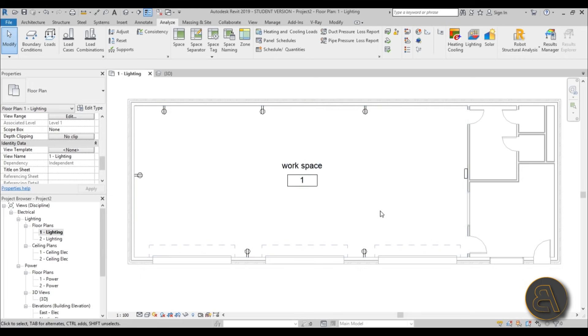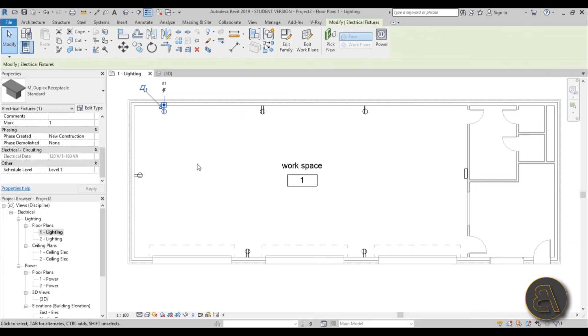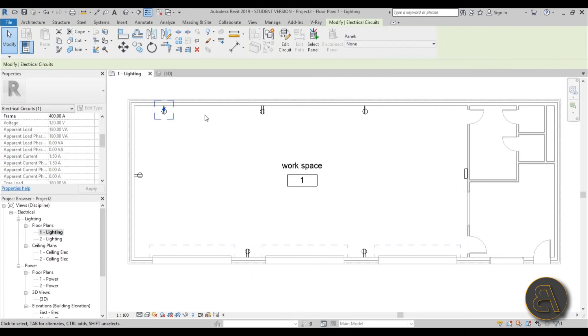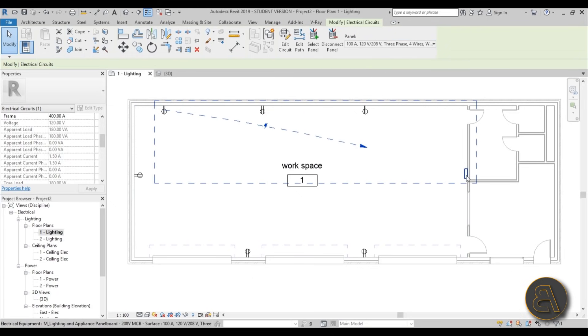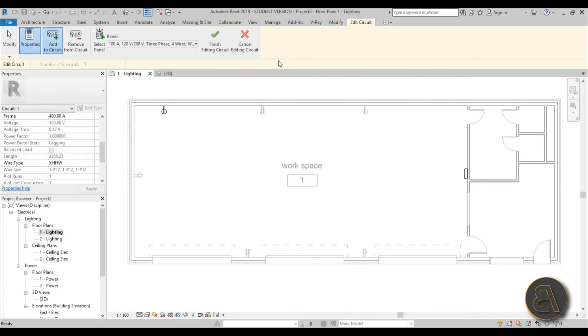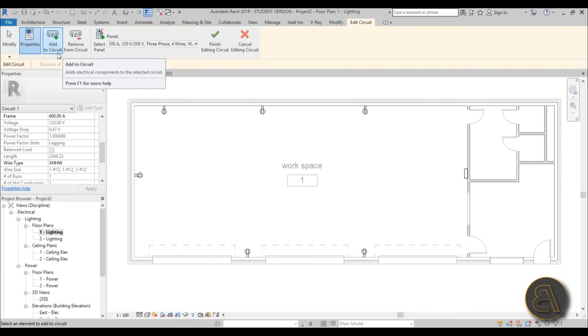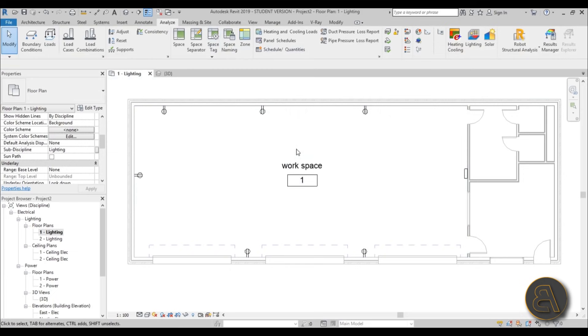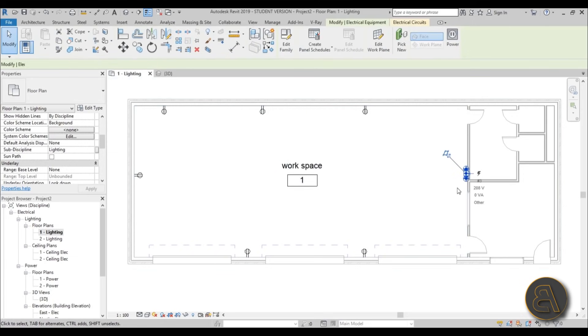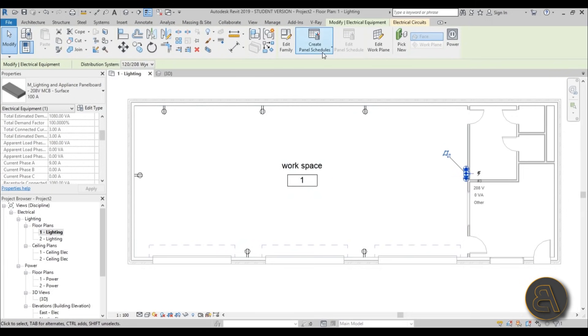Now let's create a circuit. Select one of the receptacles and go to the Power button on the Modify tab. You now have the option of selecting a panel — open the drop menu and find Panel 1. Go to Edit Circuit and now you can add more receptacles — go all the way around attaching all of them. You can remove or add them using the options here. Hit Finish Circuit and everything is now connected in a circuit.